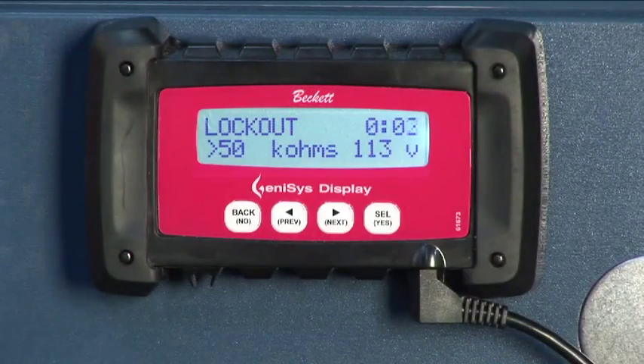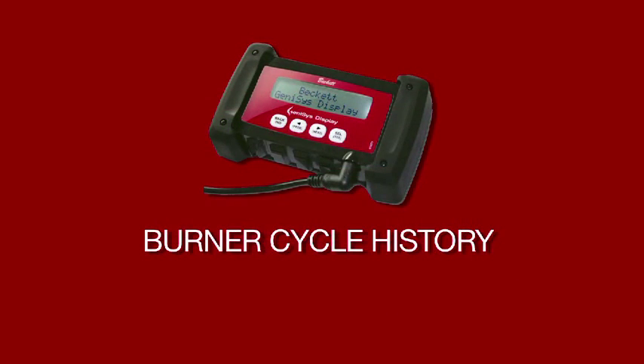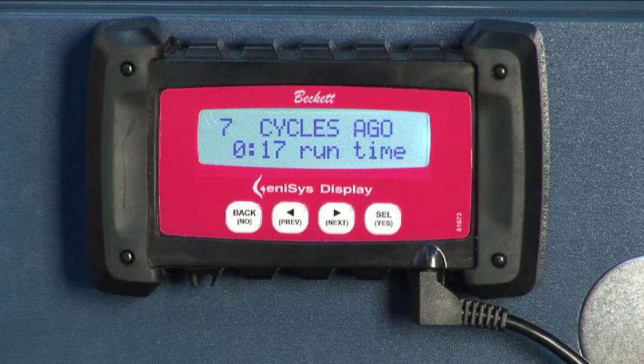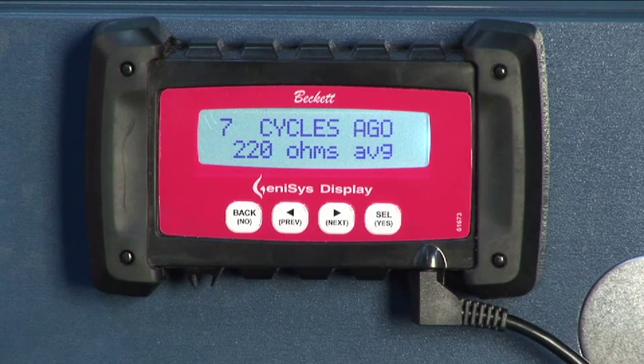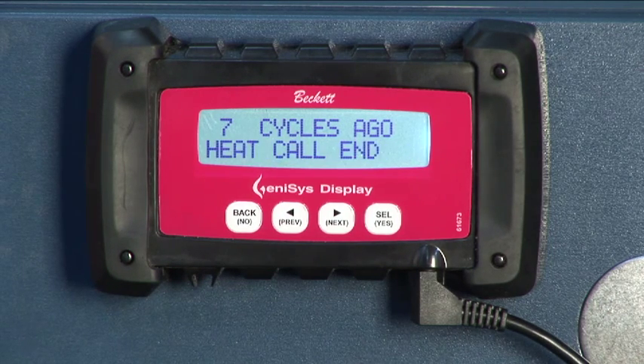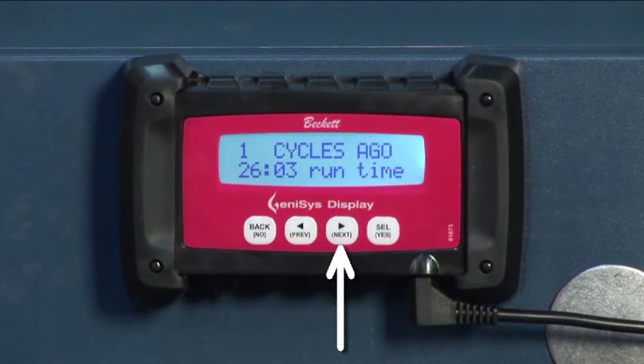Lockout: When the control goes into hard lockout, a message will be displayed on the screen that indicates the reason for the lockout. Our second functional category, the burner cycle history, shows seven different screens. These include run time displayed in minutes and seconds, to light displayed in seconds, ohms max, ohms average, and average volts displayed for the total run cycle. End reason includes nine possibilities, and off time is displayed in hours and minutes. From the burner status screen, press the next key to display the view burner cycle history screen.